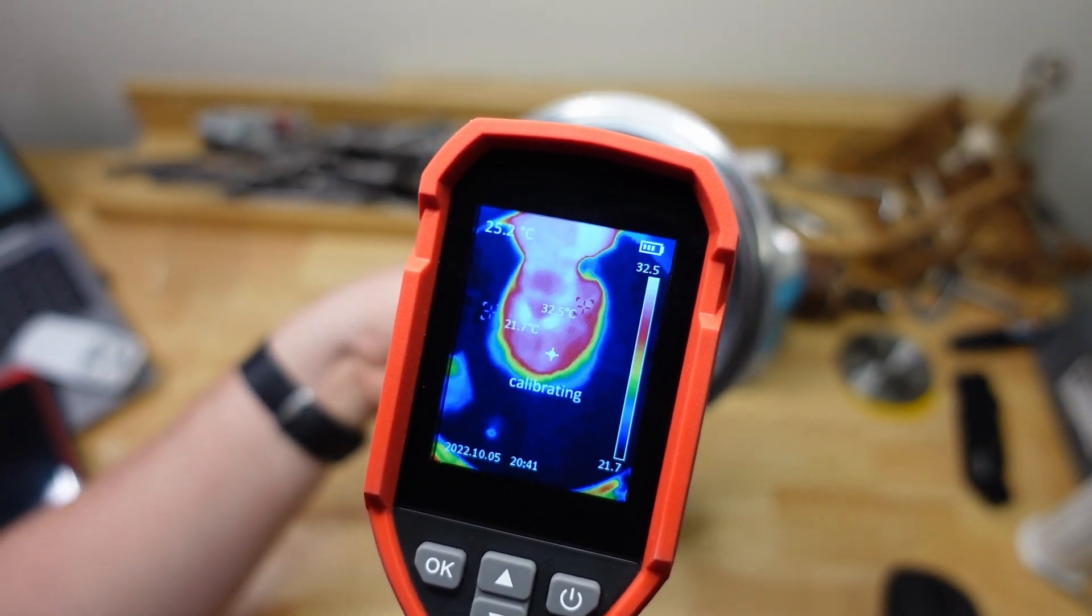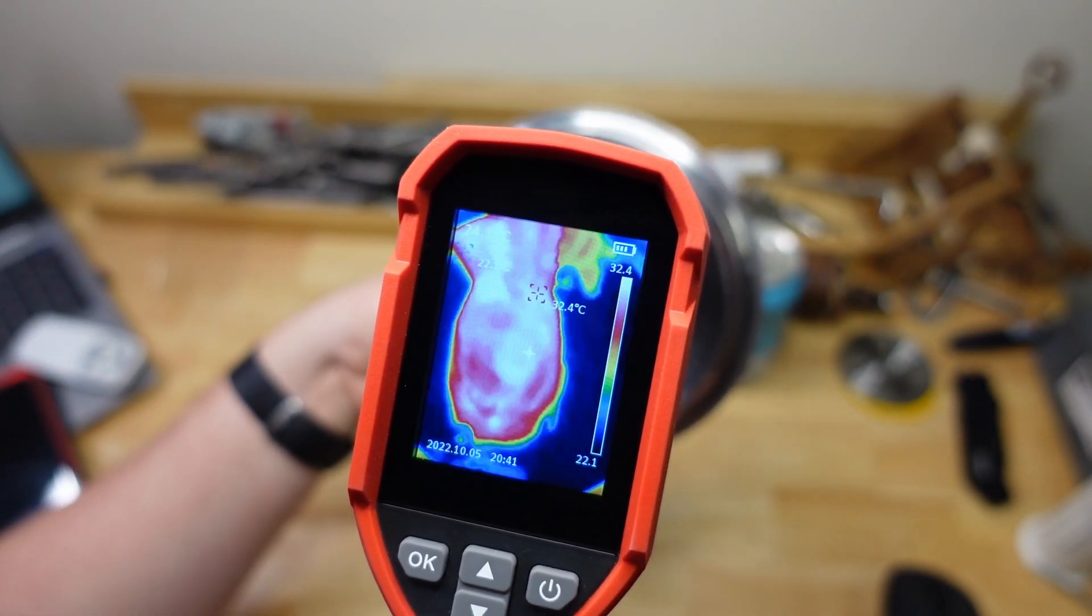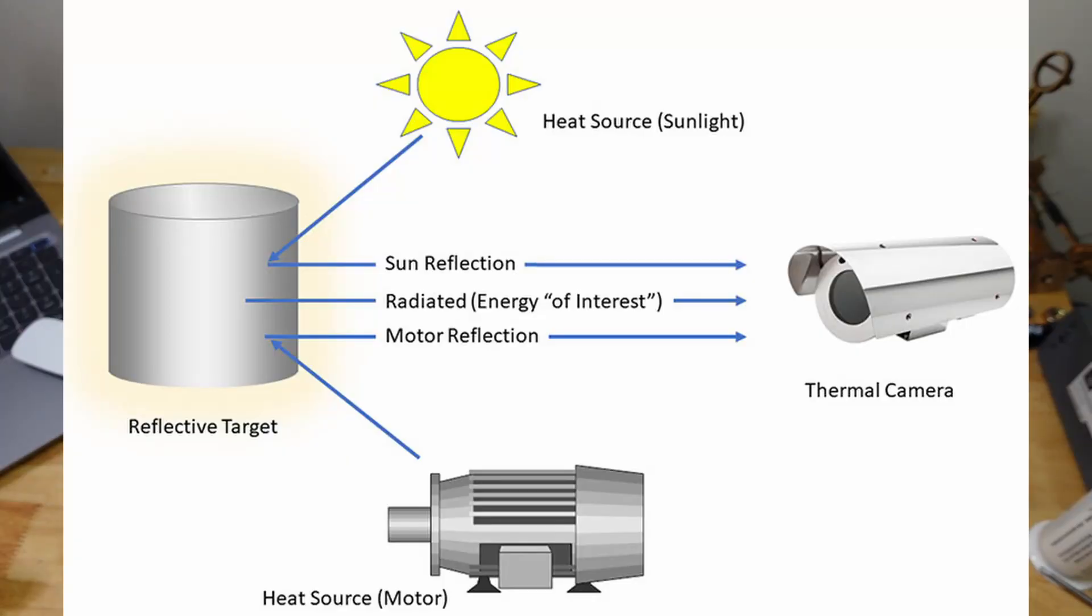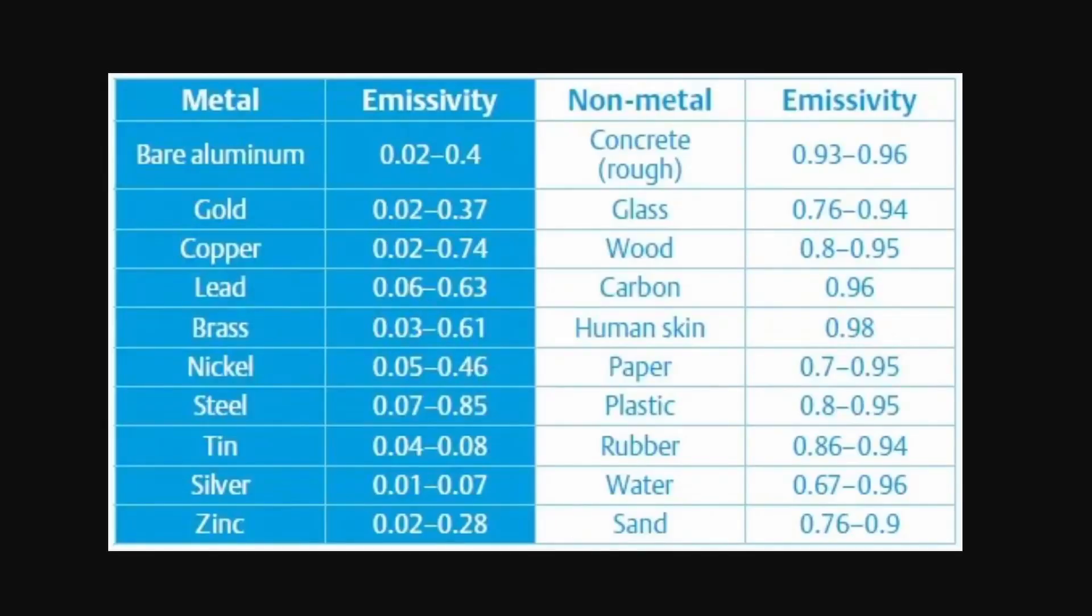And that leads me into the next important part of thermal imaging, which is emissivity. So the emissivity is a property of materials that describes how much heat they're going to be emitting versus like reflecting or absorbing. So you can look up emissivity tables, and then you can plug these numbers into your camera, depending on what you're measuring.